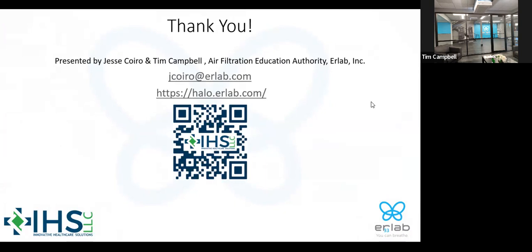I'm going to start with the first question: how long do the filters last? On average, the filters last between 2 to 5 years, so we'll give it a 3-year average before replacement needs to be done, and we will manage that for you. We have filter safety specialists; working with laboratories at the molecular level, they're changing filters much more frequently, but in a commercial setting like many of you on this call, it's about every 3 years. They will manage that and provide up-to-date status on when you should start looking at replacing the filters. There's also a pre-filter before the first stage of HEPA filtration that needs to be replaced annually, just to capture the larger particles so we don't compromise the HEPA filter.